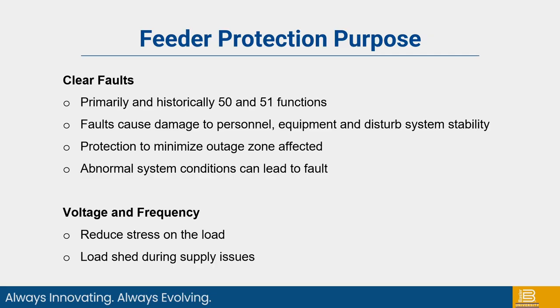Abnormal system conditions can lead to a fault, and reclosing is used a lot of times in distribution systems to try and minimize the duration of the disturbance by using the reclose function to isolate and hopefully get rid of the fault. When it recloses and goes back in service, hopefully it stays in service and doesn't have to trip out and drive to lockout.